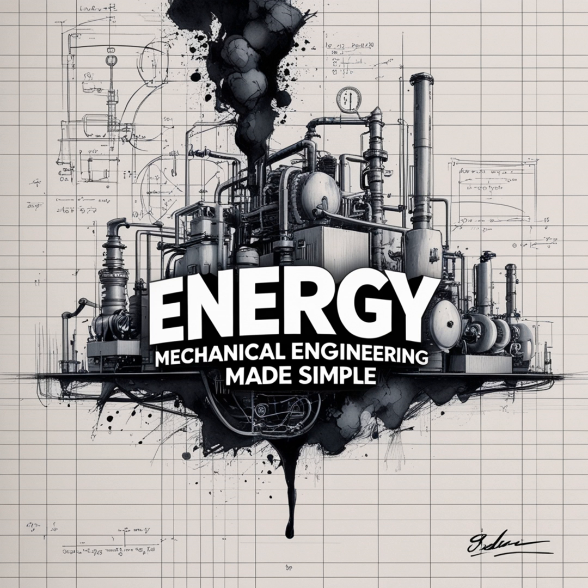Flow rate, Q, is directly proportional to speed, N, so half the speed, half the flow. Simple enough. What about the pressure, the head? Head, H, is proportional to N squared. Half the speed, 1/4 the head. N squared. Okay. And the power needed to run it. That must be the important one for costs.